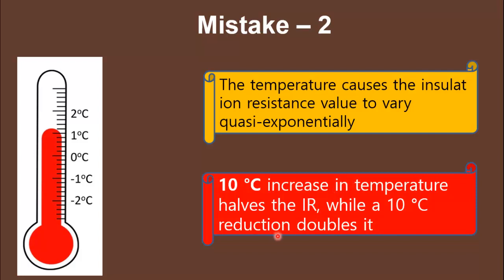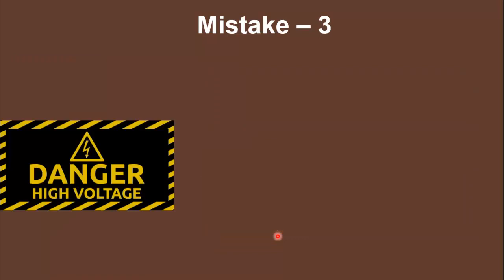Conversely, a 10°C reduction in temperature doubles the resistance value. This means whenever you perform a Megger test, you should also record the ambient temperature. The next time you test the same equipment, you must apply a temperature correction factor if the ambient temperatures differ — otherwise you will get a different resistance value on the same equipment and incorrectly judge the insulation condition.